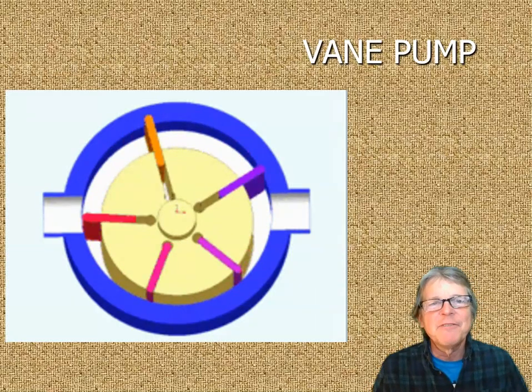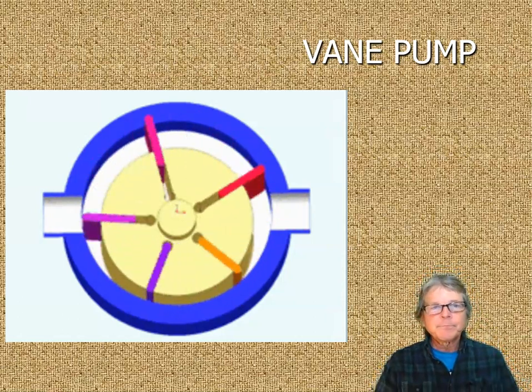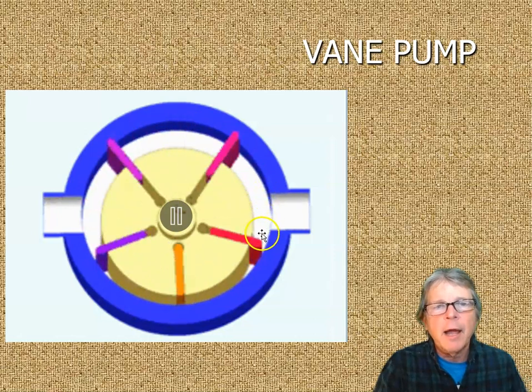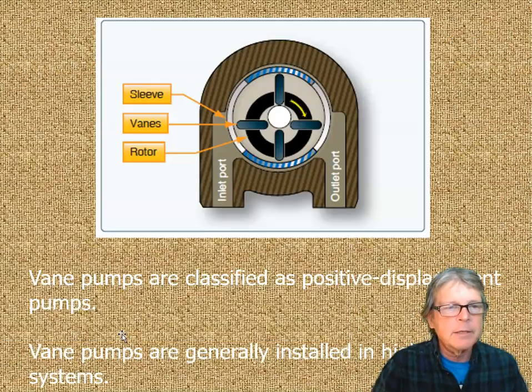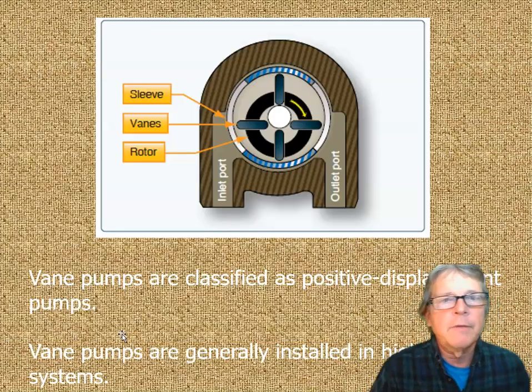This is the vane pump. So here's the vane pump. Now, the vane pump has what we call sliding vanes. So looking at the vane pump, we're going to break this thing down, but fluid comes in here. It's scooped up by the paddle wheel. It's squeezed around here. But if you notice, the further around, it starts to squeeze it, squeeze it down, and then you can't. These are really almost touching. The fluid can't get through the bottom. So here it's sucked in. This area gets bigger, bigger, bigger, smaller, smaller, smaller, and it's squeezed out this side. That is the vane pump.